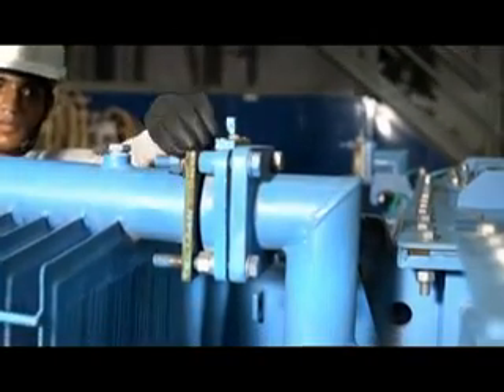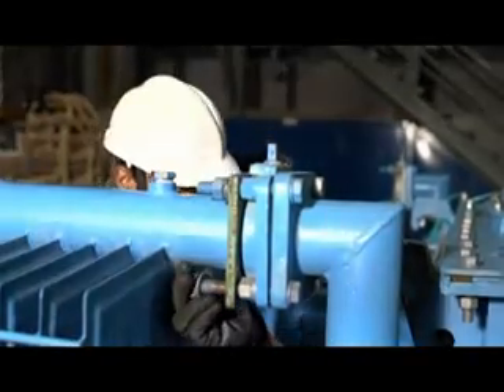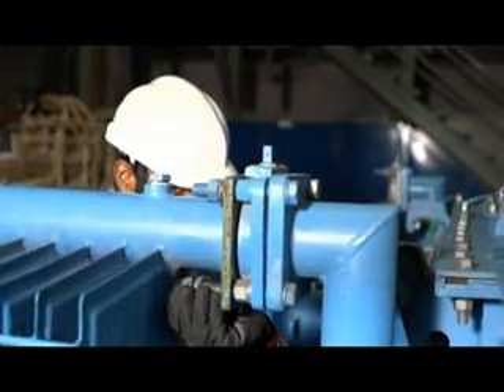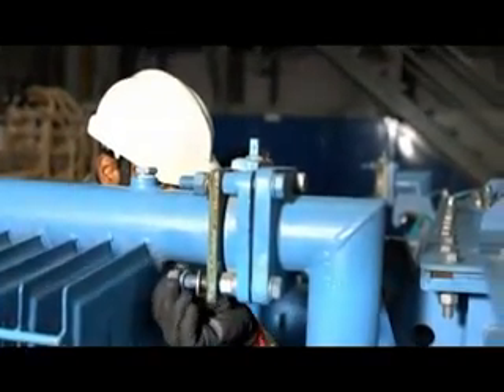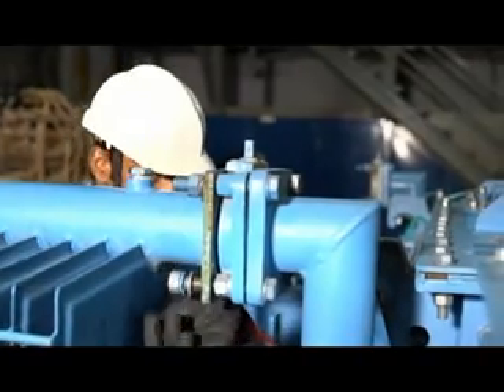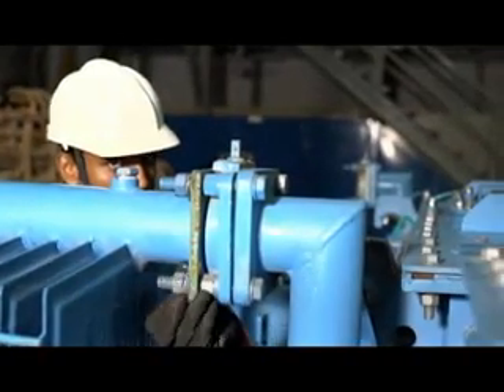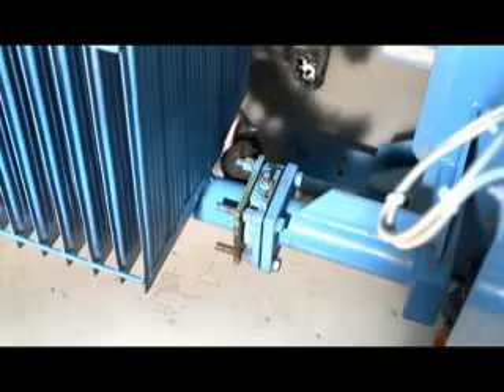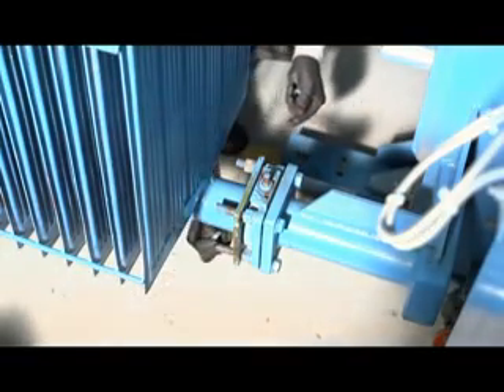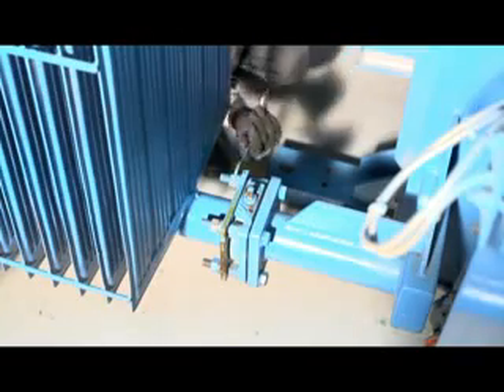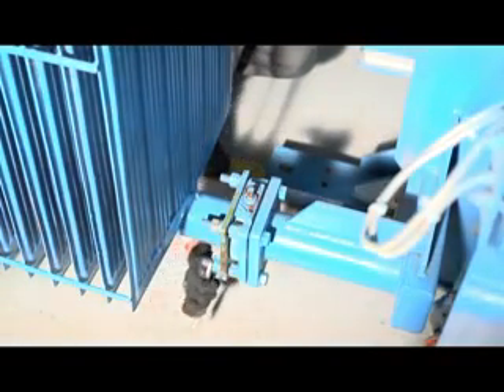When an electric transformer is loaded, current starts flowing through its windings. Due to this flow of electric current, heat is produced in the windings. This heat ultimately raises the temperature of the transformer oil. We know that the rating of any electrical equipment depends upon its allowable temperature rise limit. Hence, if the temperature rise of the transformer insulating oil is controlled, the capacity or rating of the transformer can be extended up to a significant range.